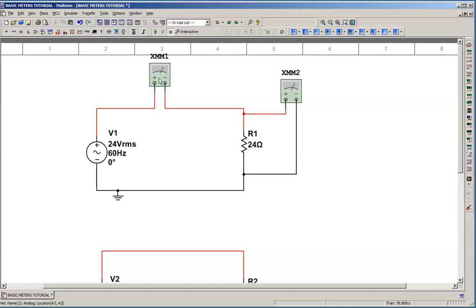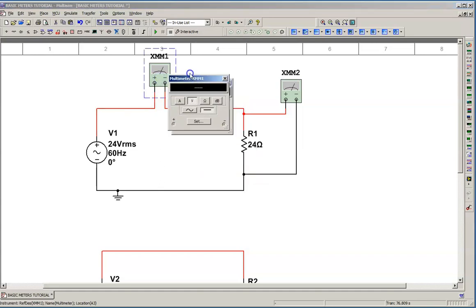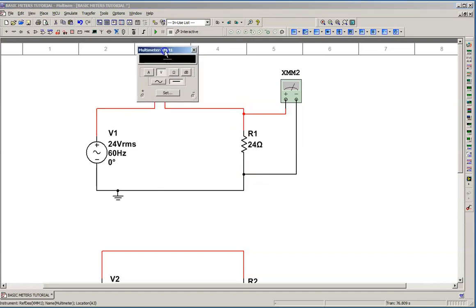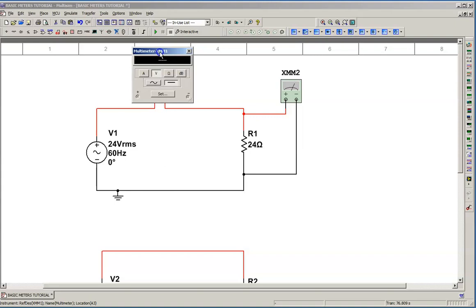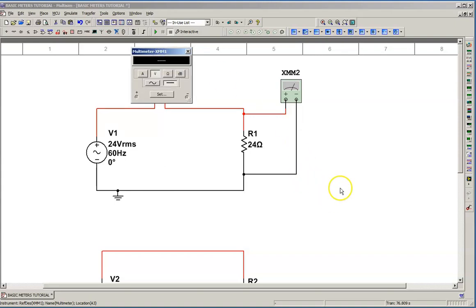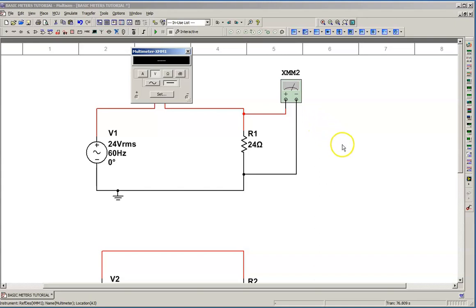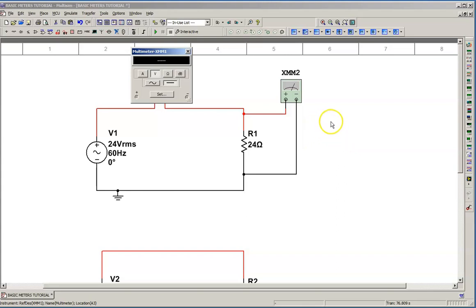Now, you can only measure 10 amps or less, typically, when you're measuring current like this. So, if you work in instrumentation or you work in automation where you're measuring power supplies or controls for PLCs and solenoids and other devices and sensors, you would use a meter in this configuration. If you're working a lot with AC, you're measuring heaters and hot water tanks and motors, you're probably going to have a clamp meter, which is a lot safer meter to work with. But keep that in mind.